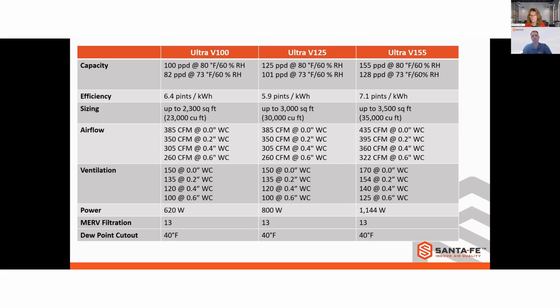I mean, you have 7.1 pints per kilowatt hour. That's a lot of dehumidification for very little energy use. And again, that eco technology is really helping us with that. And then we do size our units conservatively on square footages. We'd rather have you have a little bit more capacity than you need, but that V100 about 2,300 square feet, the V125 about 3,000 square feet, and then that V155 up to 3,500 square feet, excuse me. And again, that's up to. So if you're right on the line, you might want to move up to the next size.